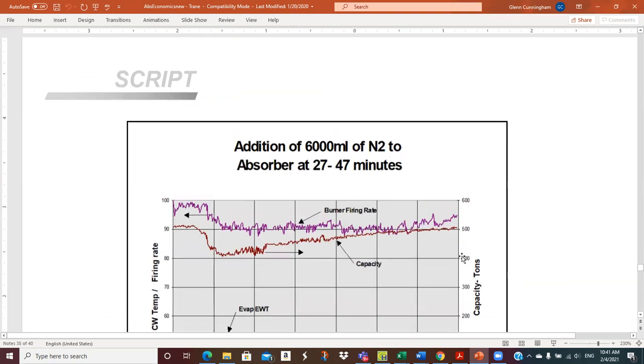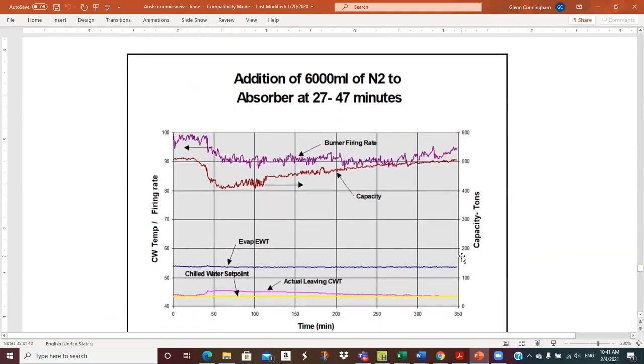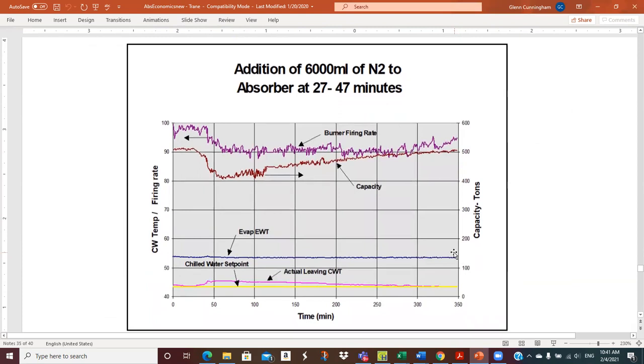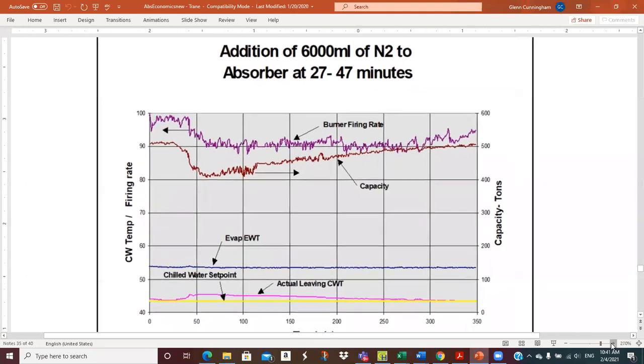Okay, so this is where they actually provided some test data where they have done various testing on their units. So in this one, between 27 and 47 minutes, they're going to inject 6,000 milliliters, or 6 liters, of nitrogen to simulate an air leak into the machine. So right in here, you can see where they start putting in this nitrogen. I'll blow that up a little bit so you can see.